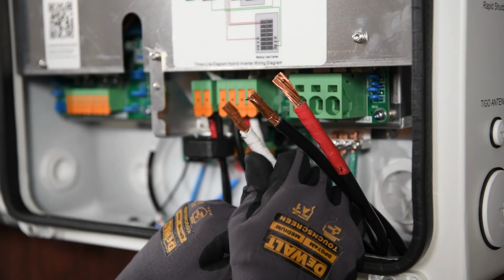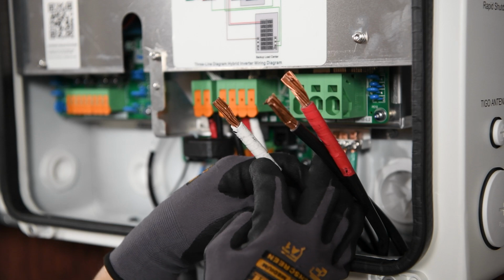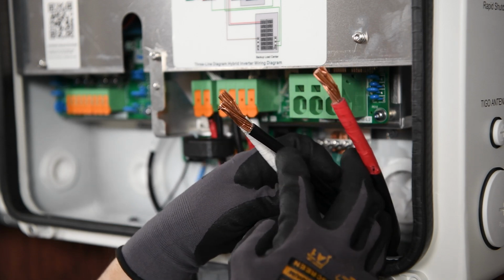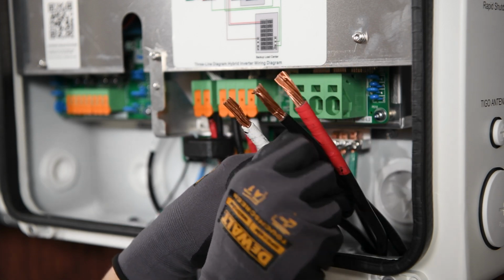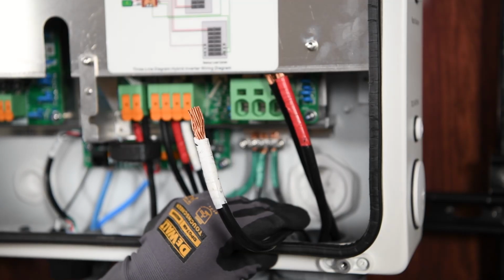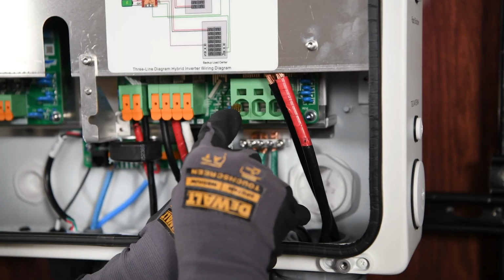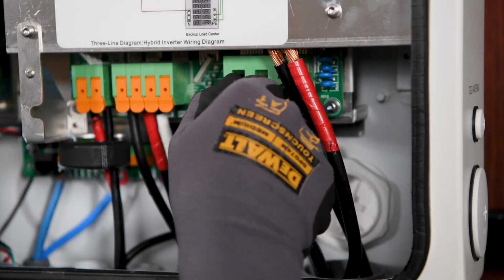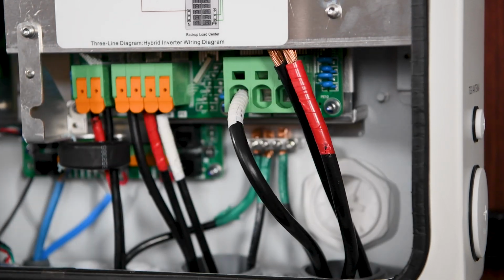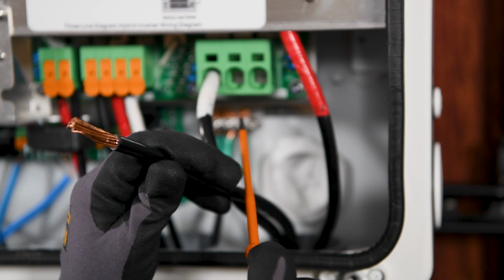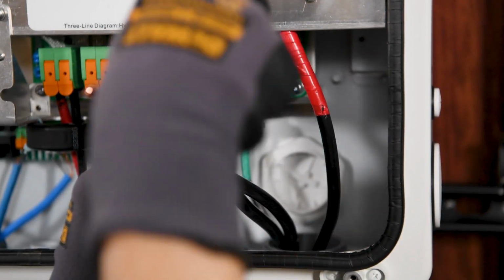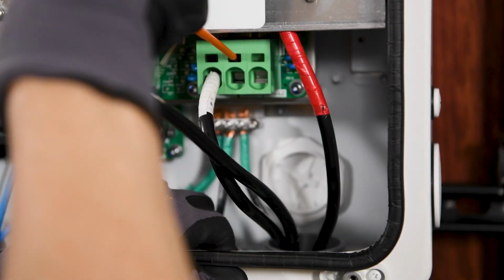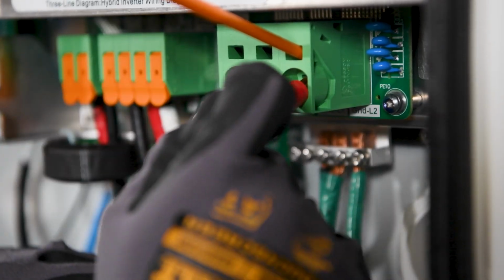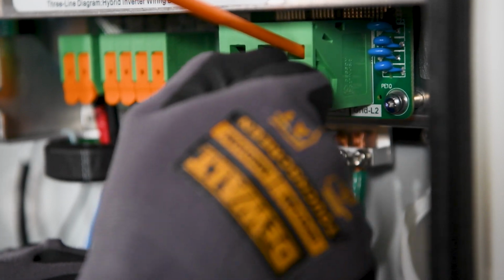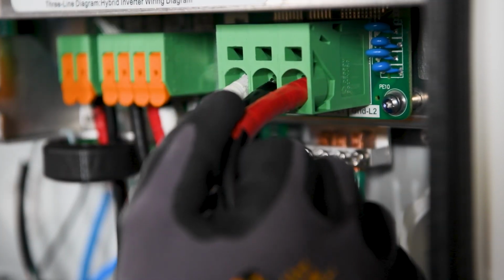So again, we've got to make sure we stay consistent with our white being neutral, our L1 being black, and our L2 being red. You should be able to insert these into the terminal input and give it a firm push, and the jaws will clamp down. If you have trouble getting your wire inside of your terminal block, you can insert a small screwdriver inside this upper rectangle to open up those jaws, and then insert your wires, and then you can release your screwdriver and those jaws will clamp down on your wire.